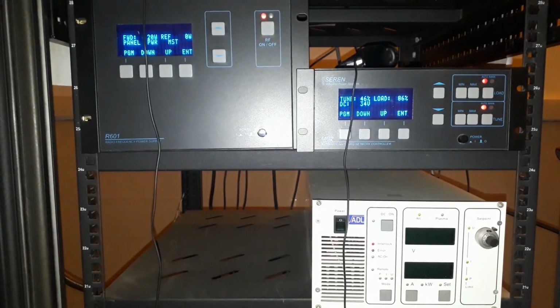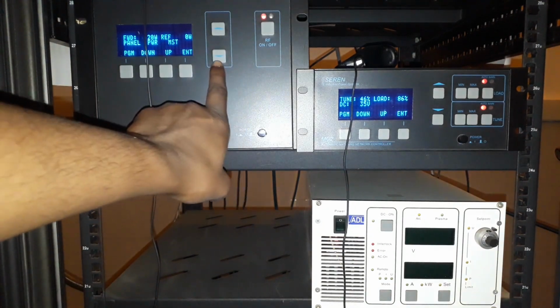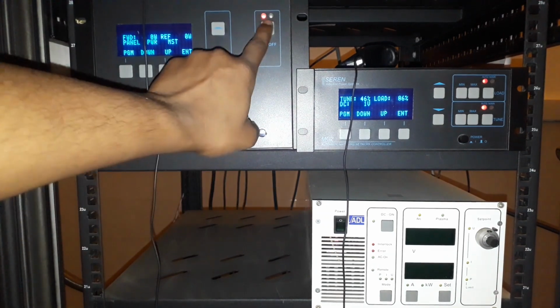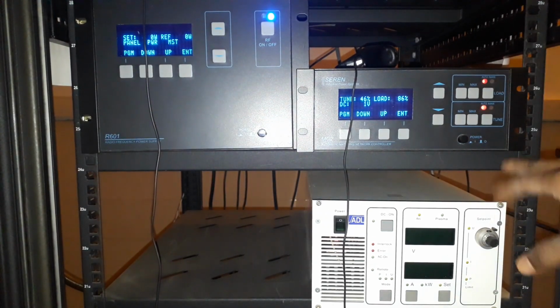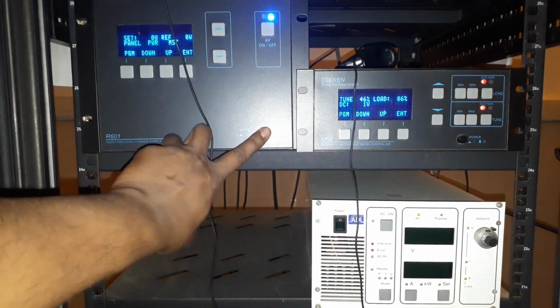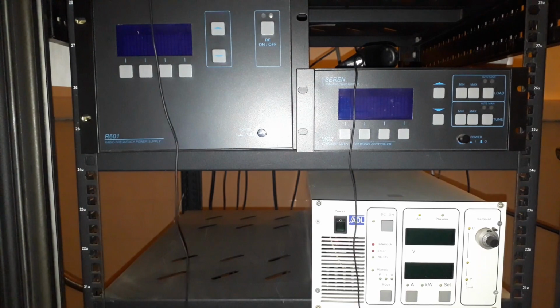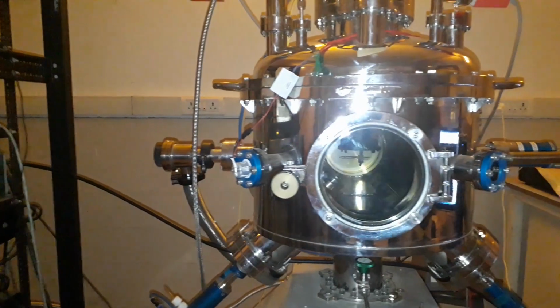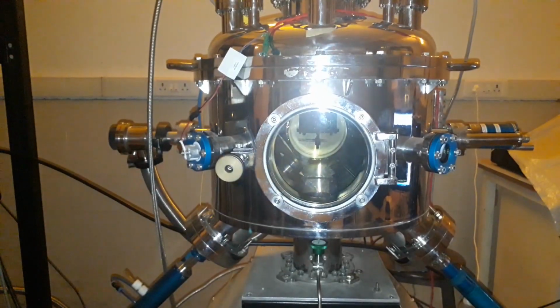I'll show you here again the same thing. Right now you see the DC voltage is 34 volt, it's 100%, reflected power is 0, and forward power is 20 watt, which is pretty much good. As soon as we are done, we can record this on the thickness monitor, whatever thickness you want. We are done, we'll bring it back to 0 watt and turn off this one. You always turn this off and then turn this off. You look at your sputtering chamber, the plasma is gone, and that's all.